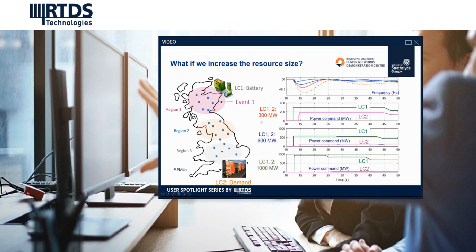But now, if we increase this number to 1 gigawatt, we can see that local controller 1 has sufficient power to cover the whole event. And that means we no longer need anything from local controller 2, because local controller 1 has a higher prioritized ranking in the table because it is closest to the event location. If we look at the frequency behavior, by detecting the event much quicker and with a much faster response, we will be able to control the frequency in a more effective way.